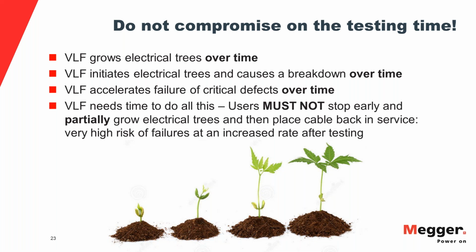This takes time. Initially, when VLF came to North America, after it was already established for over 15 years in Europe, there was a little bit of an outrage from some people, because they applied it and they had more cable failures after VLF testing than before.